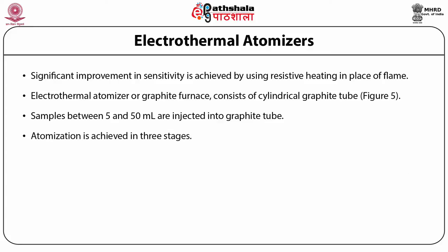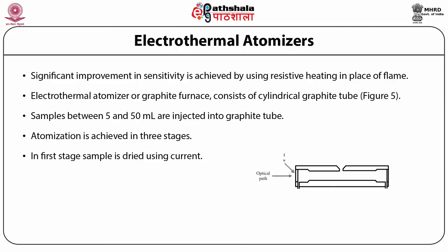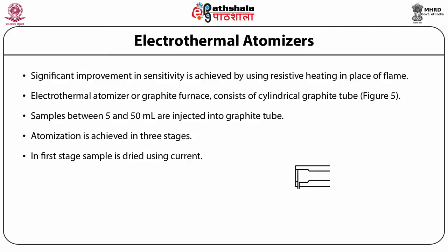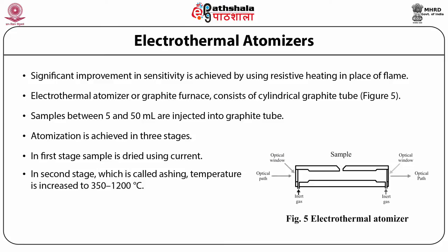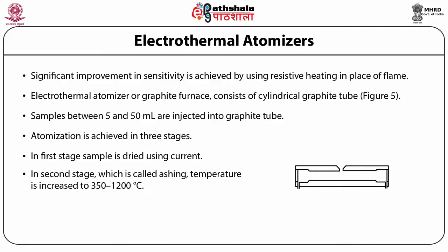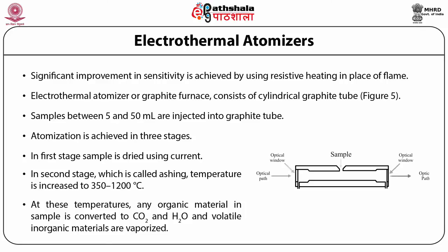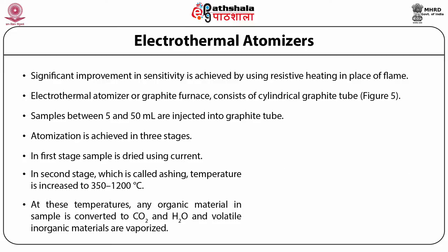Atomization is achieved in three stages. In the first stage, the sample is dried using a current that raises the temperature of the graphite tube to about 110°C; desolvation leaves the sample as a solid residue. In the second stage, called ashing, the temperature is increased to 350 to 1200°C. At these temperatures, any organic material is converted to CO₂ and H₂O, and volatile inorganic materials are vaporized. These gases are removed by the inert gas flow.